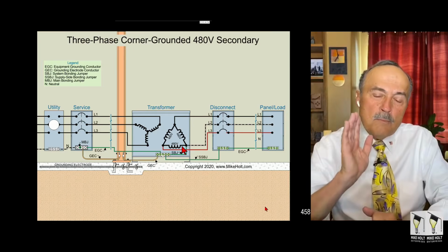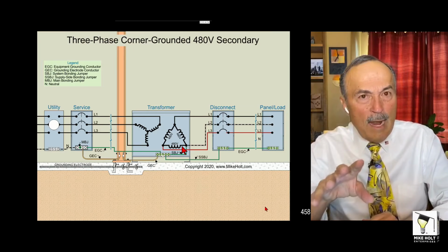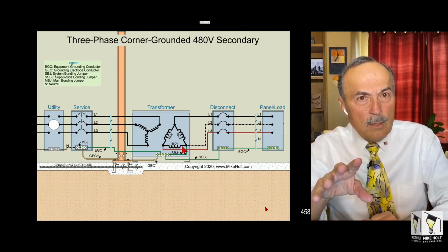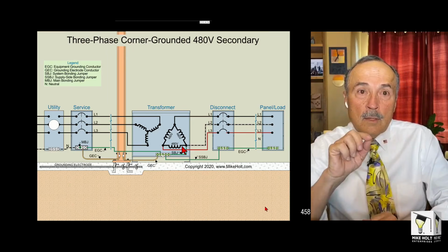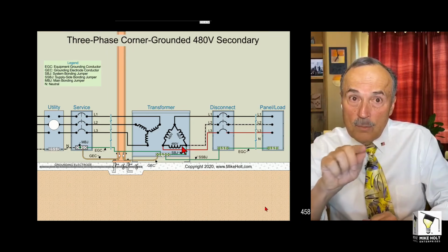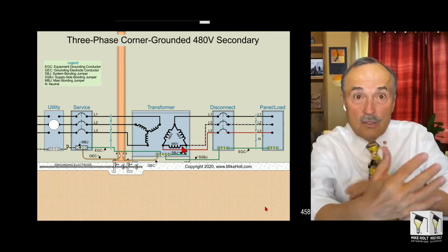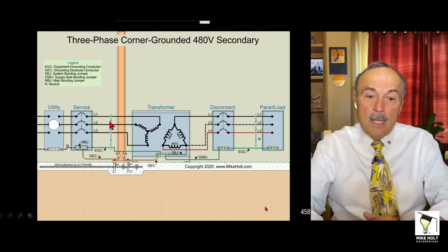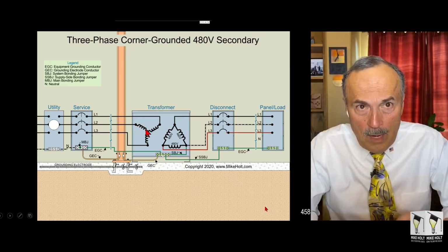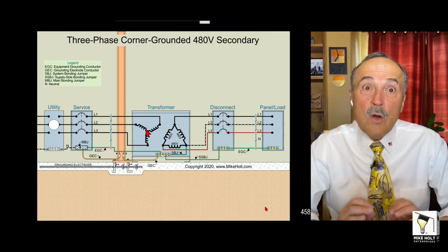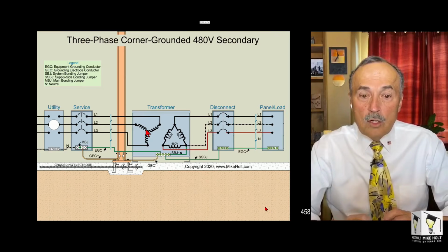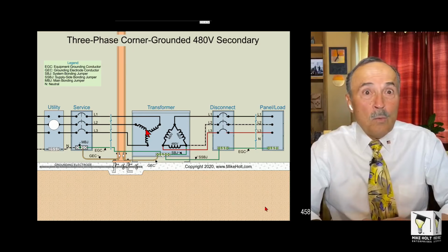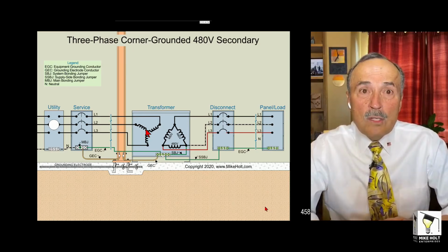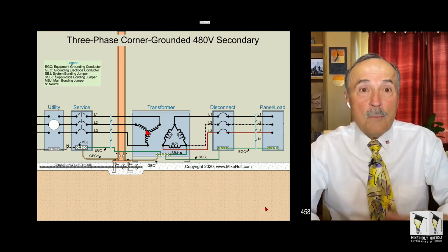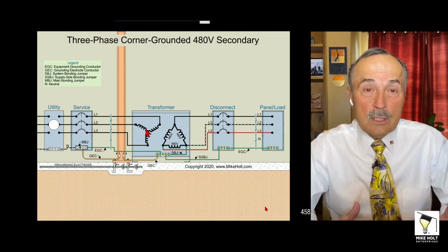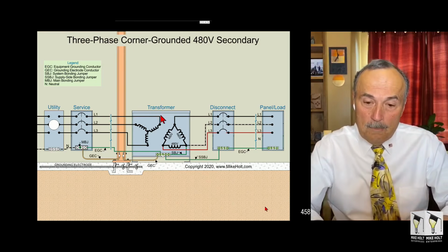I mean, supposedly, it's not the best practice to backfeed a transformer. However, you have to make sure the transformer is marked suitable for reverse fed. And you look at the instructions, they show you how to do it. So now, we do not bring a neutral on the primary side of a Y system because we don't need a neutral. Well, Mike, would it hurt if I brought a neutral there? Well, why don't you bring a neutral to 3-phase motors and not use it? So why would you bring a neutral to the primary side of a transformer and not use it? So no neutral in the primary.